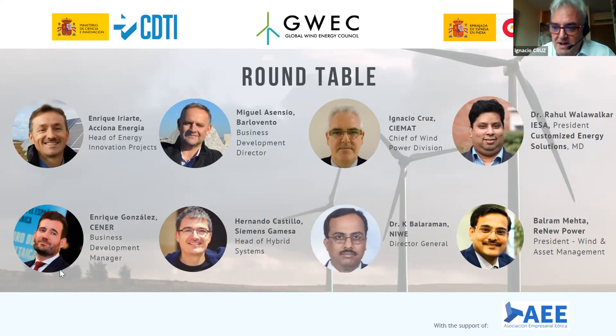Regarding converters, it's clear that the full power converter is much more recommended from the grid quality point of view than partial converter solutions like double-fed induction generation. For instance, for reactive regulation and voltage regulation of the system, full power converter can meet all the limits, while partial converter solutions depend on the rotational speed of the wind turbine.